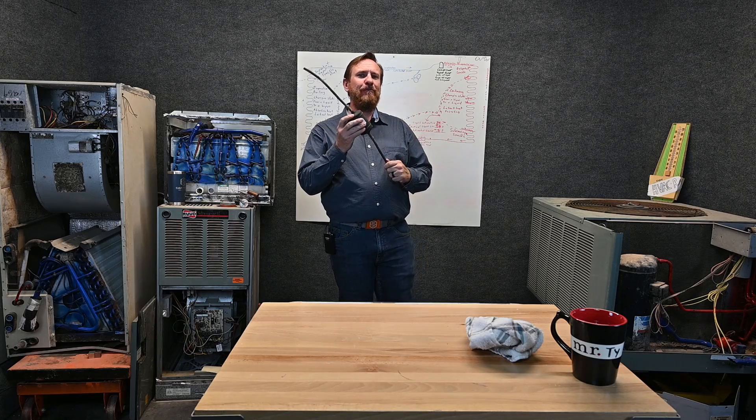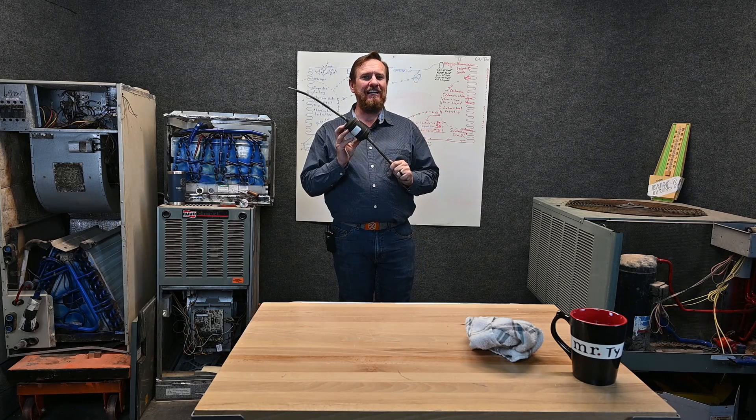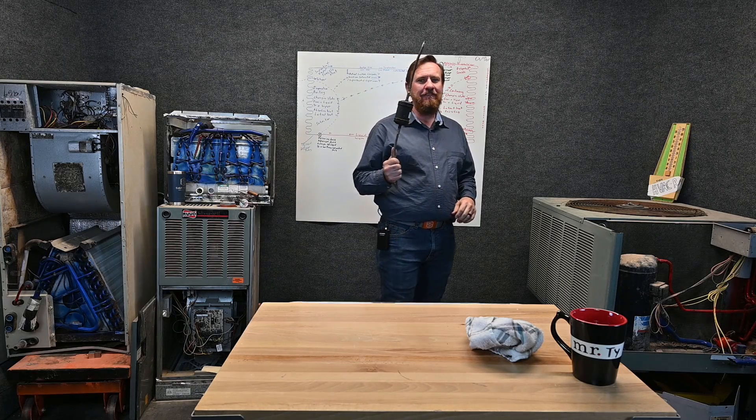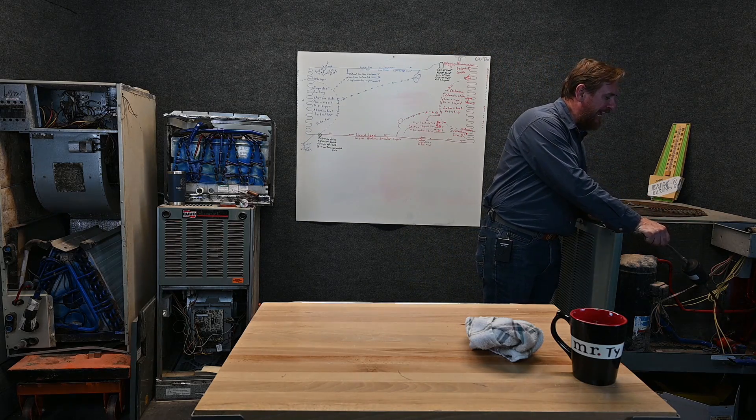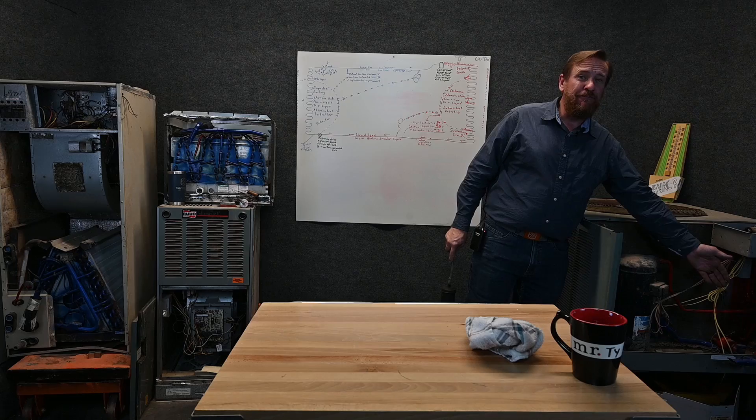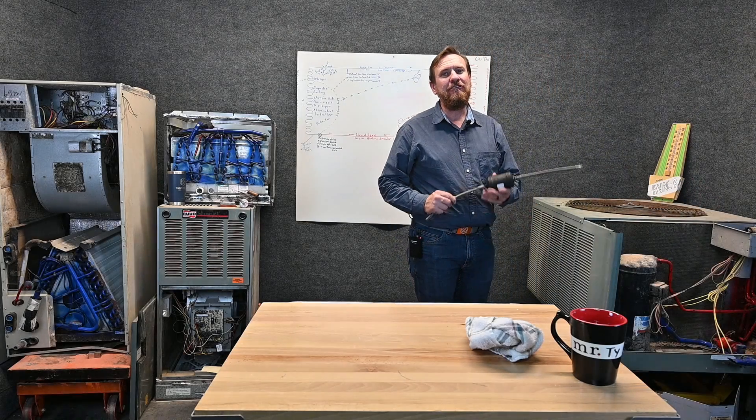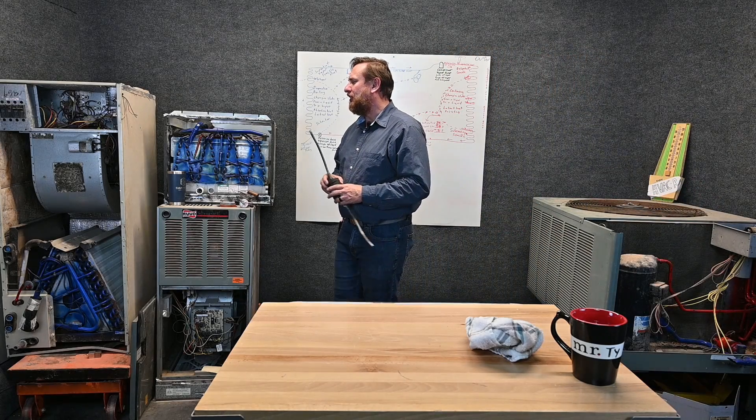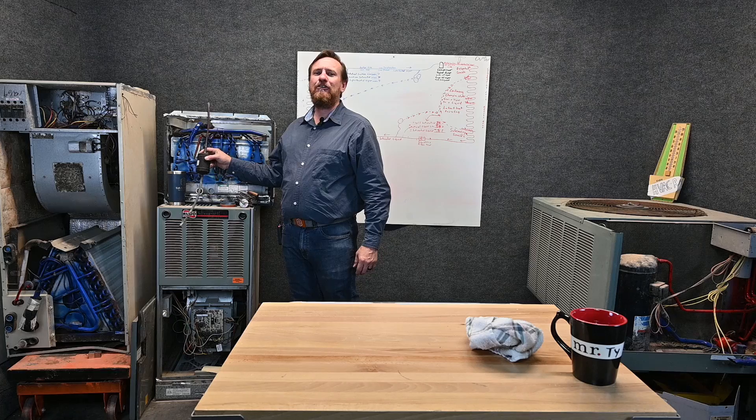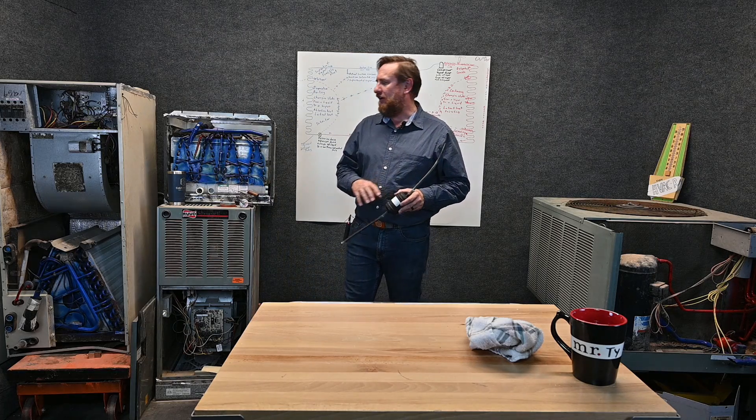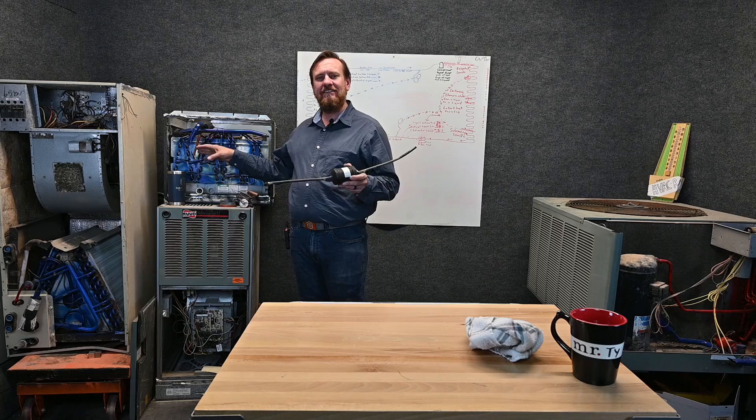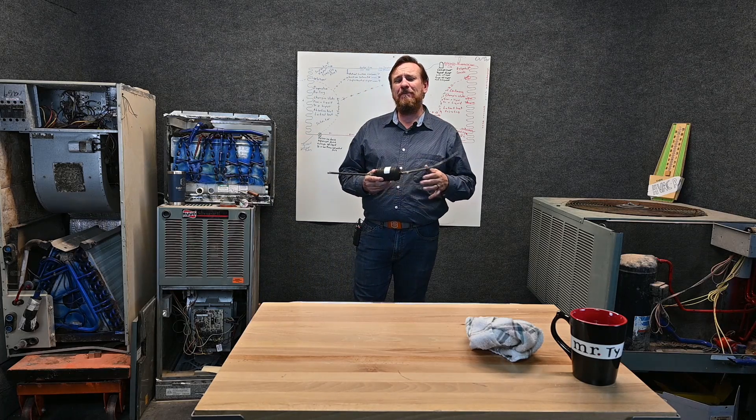This liquid line somewhere on it will have a liquid line filter dryer. Now that liquid line filter dryer can be on the liquid line inside of the outdoor unit but it's still going to be after the condenser but it may be before the valve. That liquid line filter dryer can also be located in the house right before the evaporator. Ideally your liquid line filter dryer goes before your metering device to protect it, but where that's located really depends on your environment.